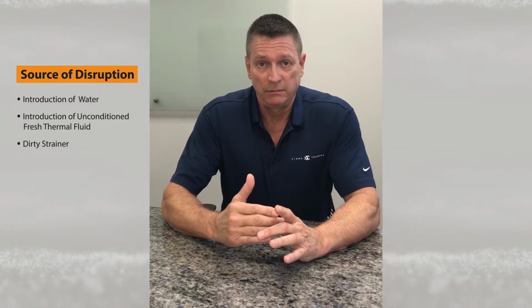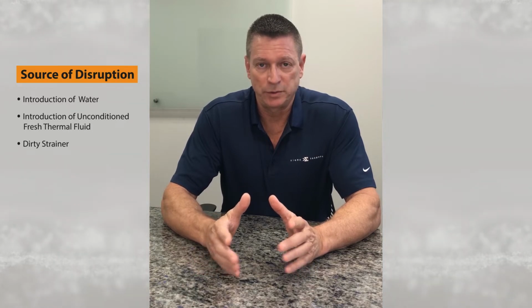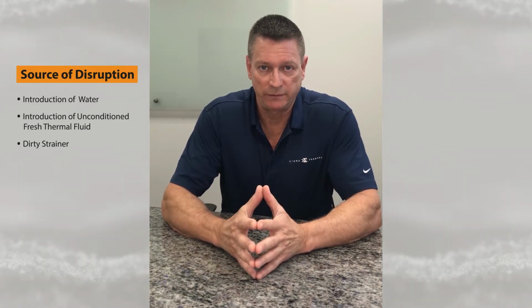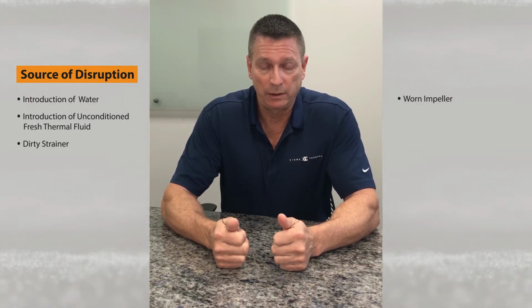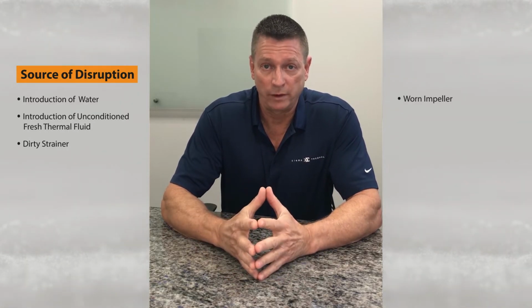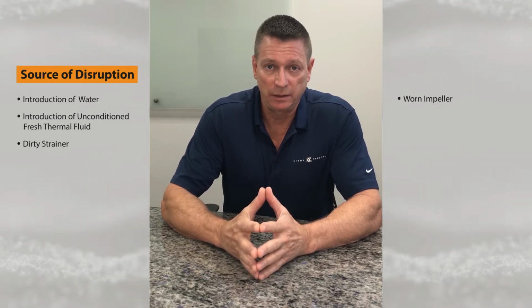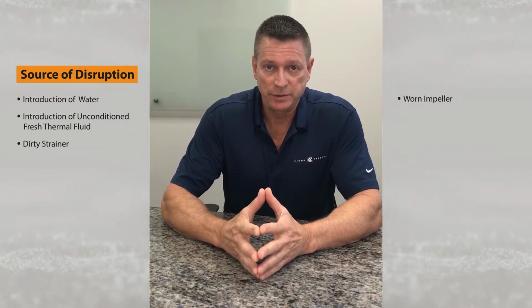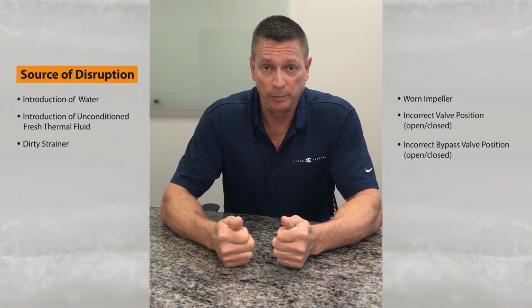If it's not, then you need to shut that pump down, cool the fluid down to a safe temperature, and pull the strainer and see if it's clogged. If it's not clogged, probably going to have to pull the impeller out of the pump because it may have worn, and they do. They don't last forever. So check the impellers, check the strainers, make sure nobody has closed a valve that should be open.